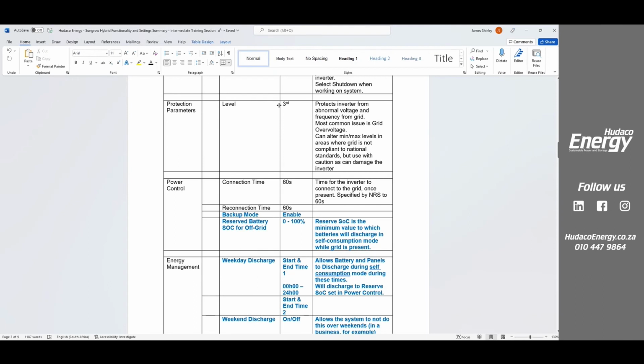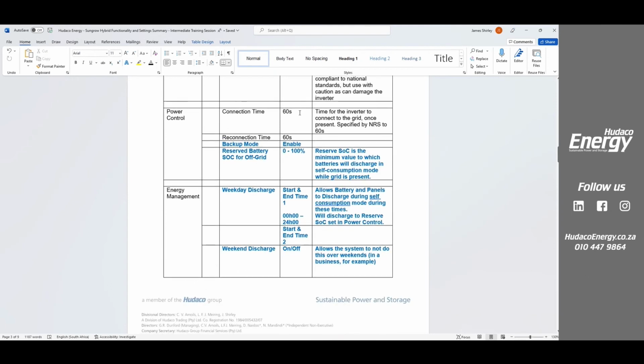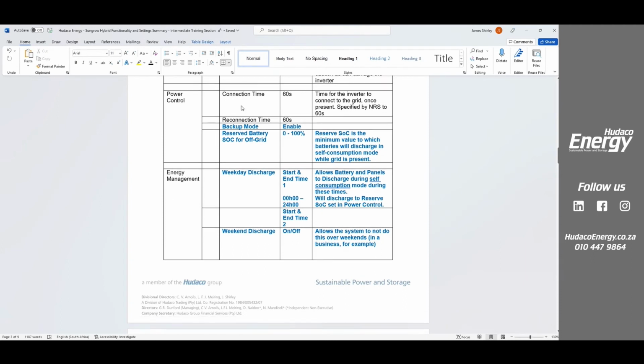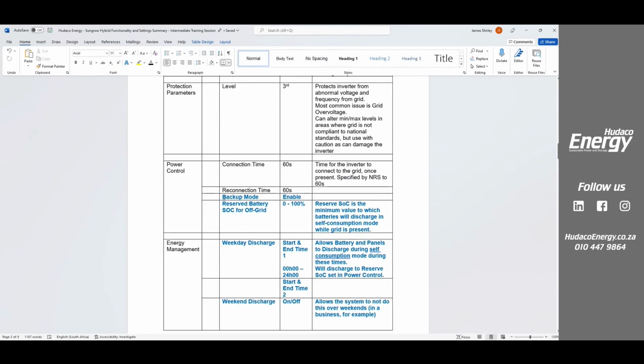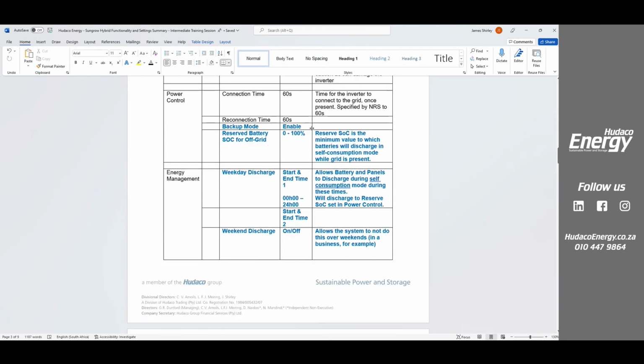Protection parameters comes as standard in 3rd level. Connection time 60 seconds. This is through NRS. Under the power control module, backup mode, enable, and reserve state of charge, we spoke about that. Set it to 35, 40, 50, 60, 70, 80, whatever percentage you like to have there.